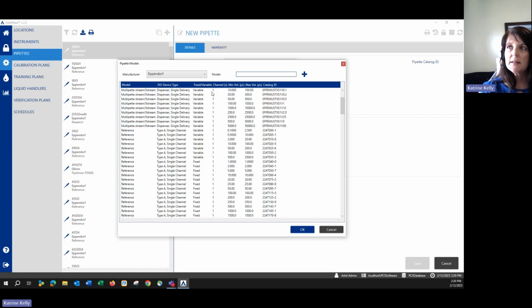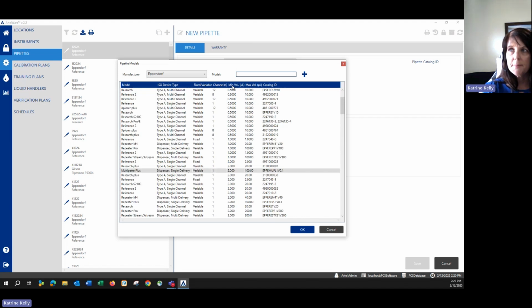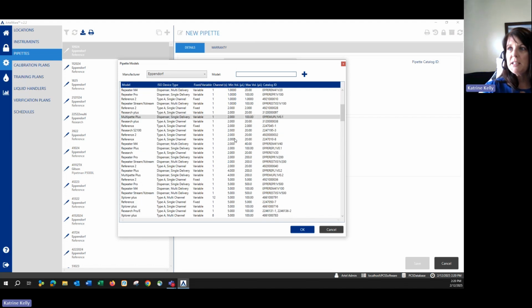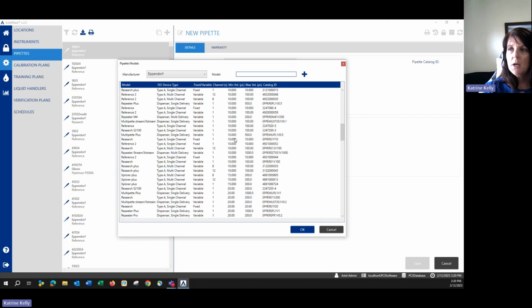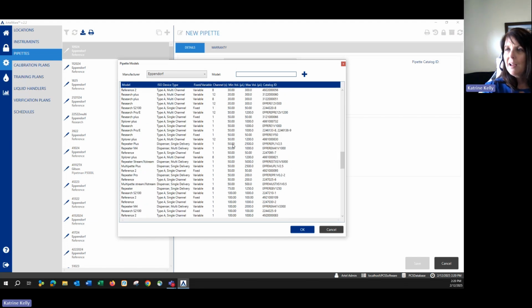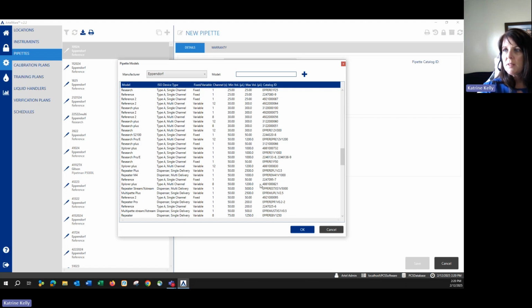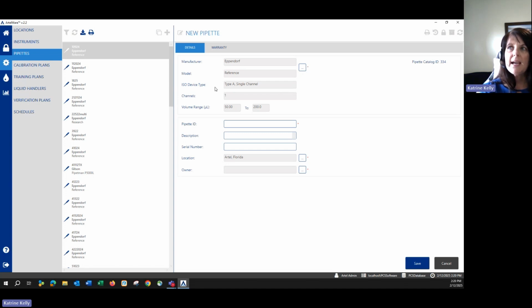Now you can sort this list by any of the columns. I usually sort by the min or max volume. So today I have a 50 to 200 microliter pipette. So I'm going to quickly scroll down to my 50. So it's a 50 to 200 variable volume pipette, single channel. See if I can find it. There we go. And it is a reference pipette. So once I find my pipette, I select it and then click OK. And as soon as I click OK, ISO device type, channels, and volume range are automatically filled in for me.